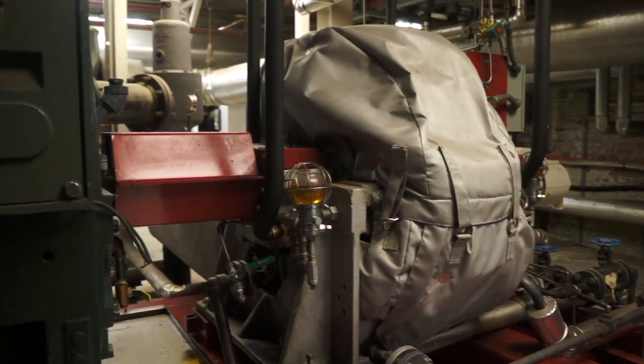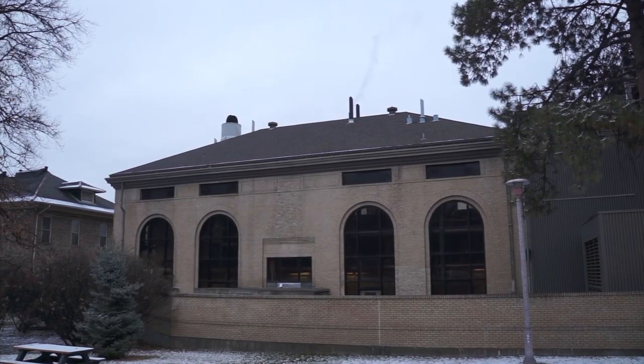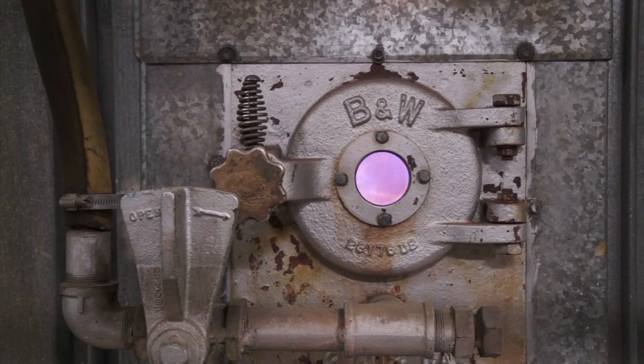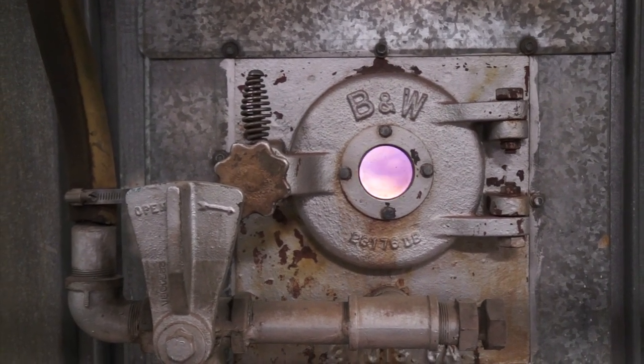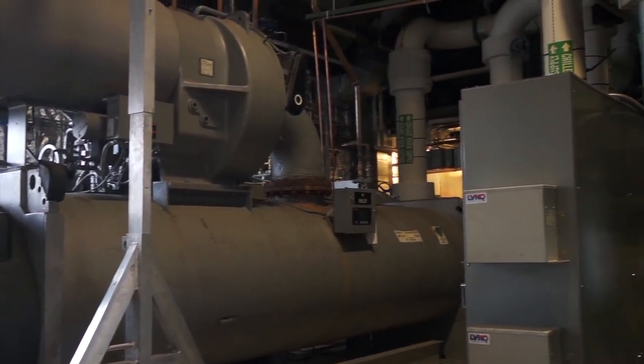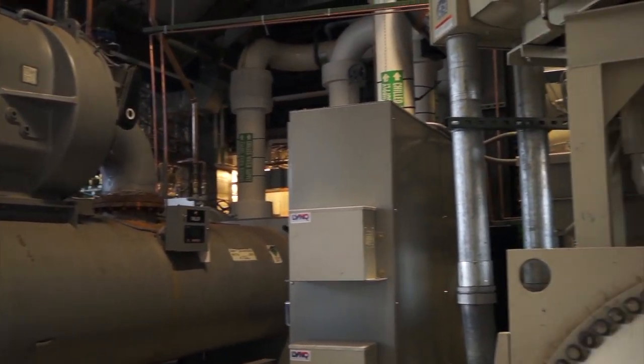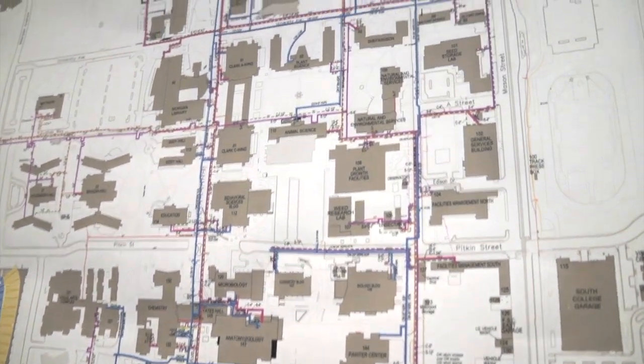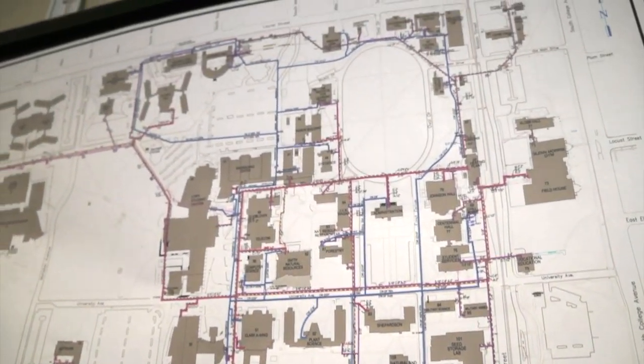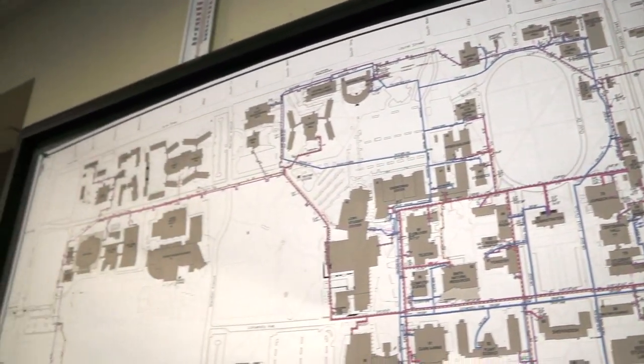Here at CSU, this is done using three boilers within the heating building. The plant has 210,000 pounds an hour of capacity. Summer loads range from 18,000 to 38,000 pounds an hour, and winter loads reach up to 170,000 pounds an hour. The steam system works using three boilers and 10 miles of pipes, five miles of which are in underground tunnels and trenches.